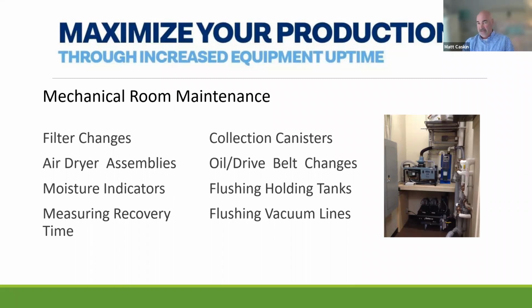Collection canisters, or solid collectors, we like to call them, on the vacuum pumps, they need to be changed out periodically. There's some screens in there that need to be changed out periodically. Vacuum systems, we look at oil changes. There's drive belts that need to be changed periodically. A lot of the dry vac systems, or all of the dry vac systems now, have holding tanks. Those need to be flushed out periodically. Vacuum lines also need to be flushed. One thing with dry vacuums, you want to make sure that you use a non-foaming cleaner. So like our partners at Midmark, they recommend certain cleaners for their products. You always want to make sure that you're using a manufacturer recommended cleaner when you're flushing your vacuum lines.